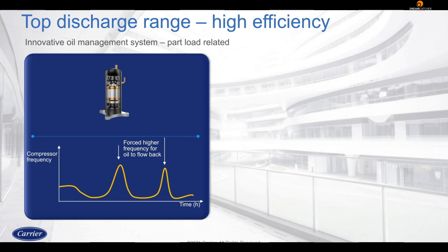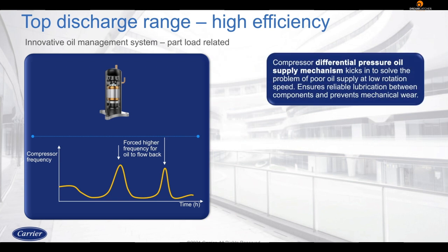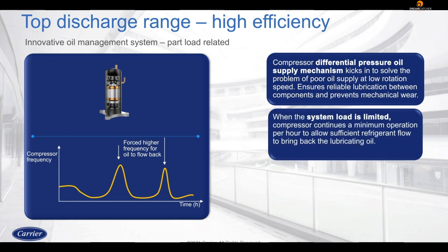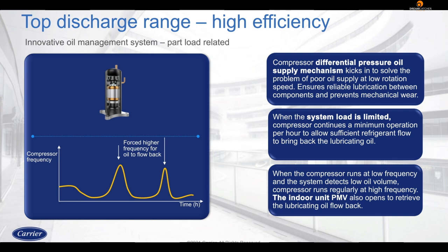We all know that the system will operate at varying capacities throughout its life, and the problem of poor oil supply at low rotation speed is taken care of by the compressor's differential pressure oil supply mechanism. This ensures proper lubrication and prevents mechanical wear and tear. And when the system load is limited, the compressor continues to operate at a minimum operation per hour, which allows sufficient refrigerant flow to bring back the lubricating oil. If the compressor is running at a low frequency and the system detects low oil volume, the compressor is run regularly at high frequency, and even the indoor unit PMV opens to retrieve the lubricating oil flowback.